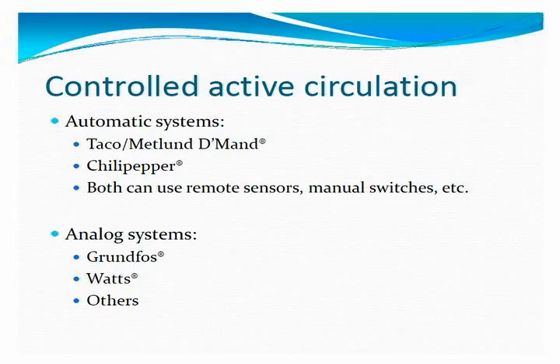There are a variety of automatic hot water circulating systems out there. Taco and Metlund have a device called Demand. This unit's been around since the late 1980s. The same manufacturer of the Metlund system has developed a system called Chili Pepper — a cute name, a good price. Both of these can use remote sensors or manual switches, occupancy switches, quite a number of systems, to only turn on that hot water system when necessary. These are great energy savers on hot water systems.